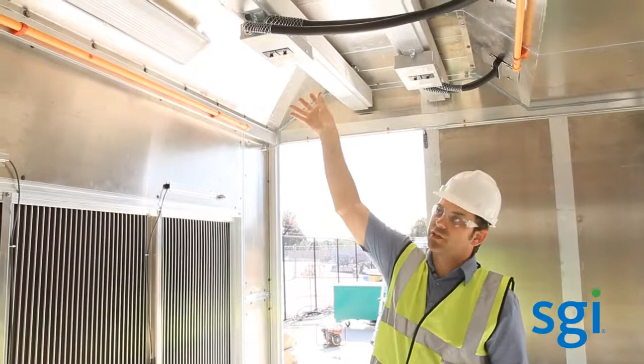So the busway that SGI offers comes in several configurations. Our standard units are pretty straightforward. They come in all the standard voltages, amperages, and hertz. And with our design to order element of our business, we're able to provide, like I said, almost limitless types of power. We can even hardwire directly from the electrical panel that we already talked about. So again, this particular unit offers, you see the dual bus bars with an A and a B fashion, and what that really results in is redundancy. So that's one of the key components of the system electrically, is offering our customers redundancy, right?